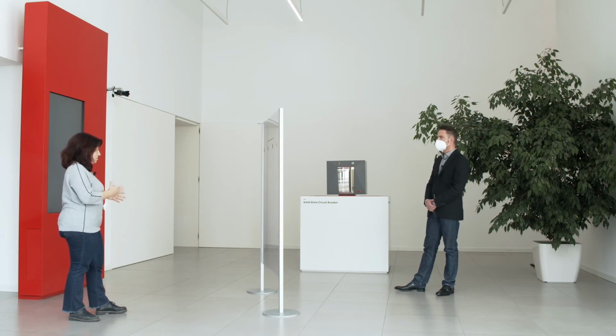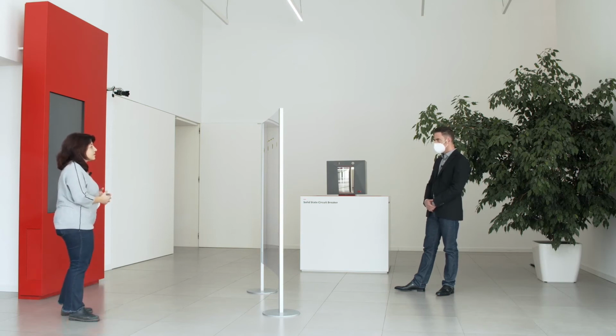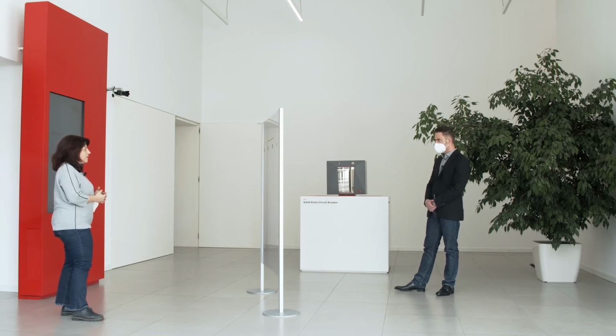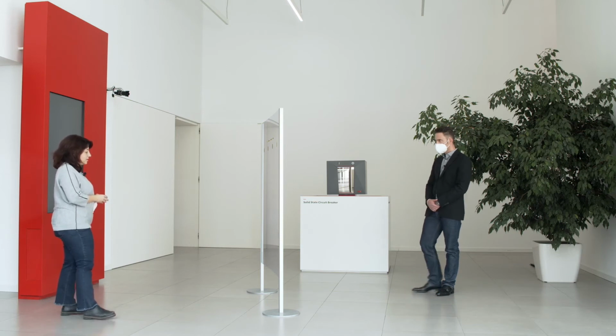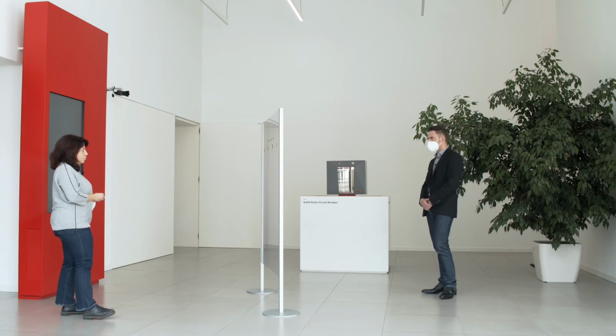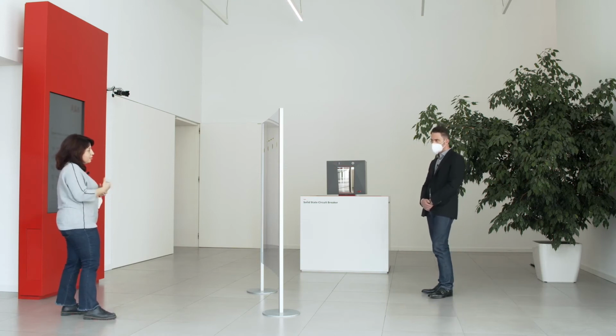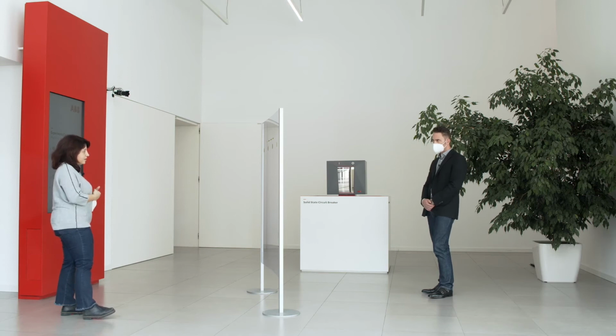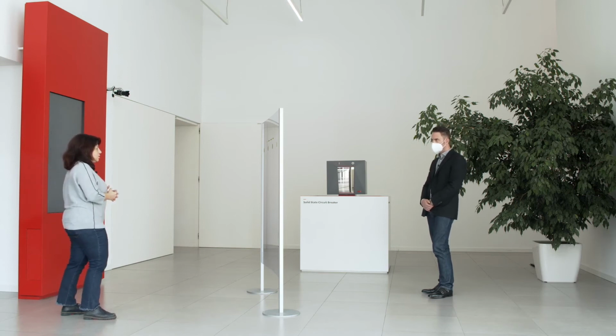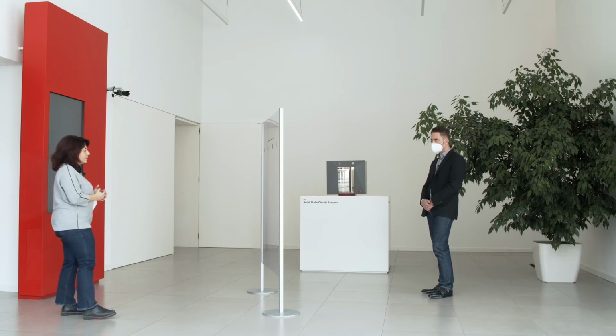Another point to consider during the sizing of the system is the fact that the internal ohmic resistance isn't constant, but its value can depend on the state of charge of the battery, on the aging, and on the external operating temperature of the battery. In fact, its value can increase with aging, can be double at the end of life of the system, and increases also when the battery works at low temperatures and low state of charge.